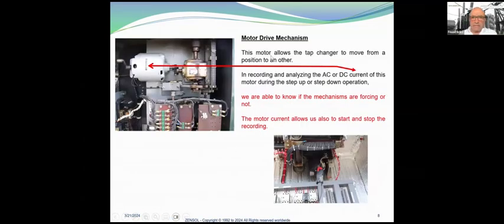The motor drive mechanism allows the tap changer to move from one position to another. By recording and analyzing the AC or DC current of this motor during the step-up or step-down operation, we are able to know if the mechanism is forcing or not. The motor current also allows us to start and stop the recording, so you have an exact window of the event.